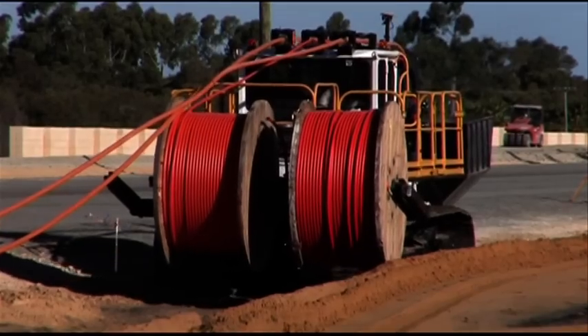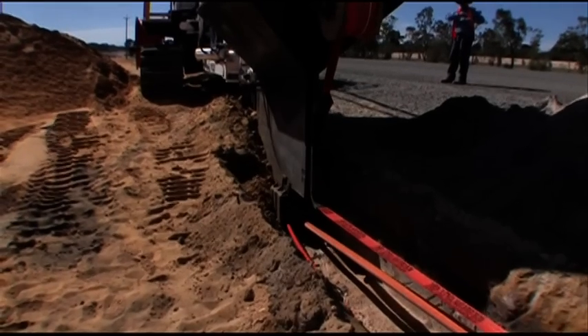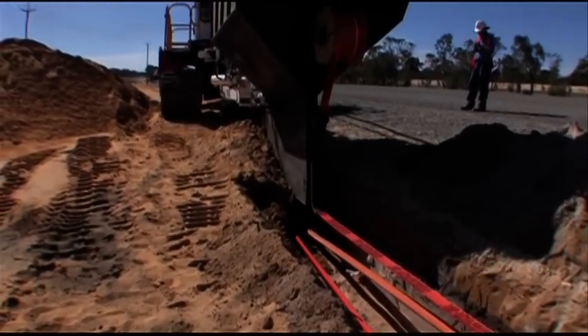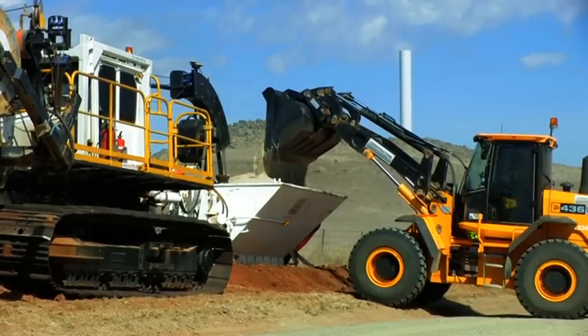Multiple combinations of power and communications cable and conduits can be installed simultaneously in single runs. The cable or pipe is laid immediately behind the ploughing blade at an installation rate of up to one kilometre per hour, depending upon the terrain, depth and diameter.